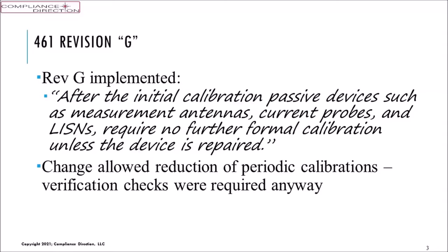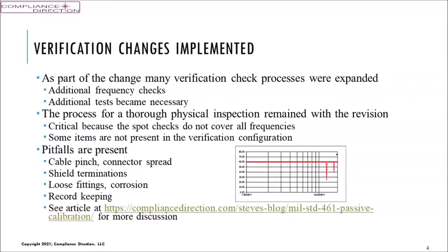So we're validating that. But the change did add some processes that expanded what we're doing in the verification checks. We did some additional frequency checks and some additional tests that became necessary because the verification previously was pretty well limited. And the process for this thorough physical inspection remained with that revision. It's critical because spot checks do not cover all frequencies, and we are putting in spot checks. Some items are not present in the verification procedures. And as I indicated, there are some pitfalls present in using the verification solely.